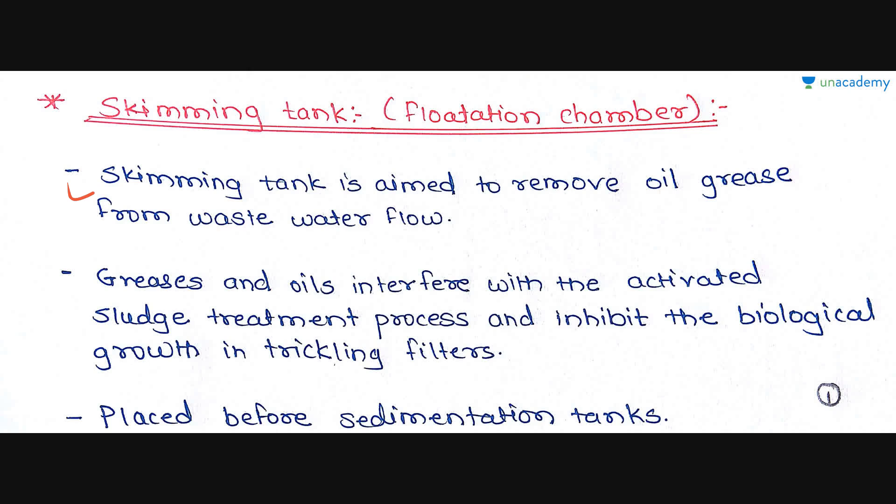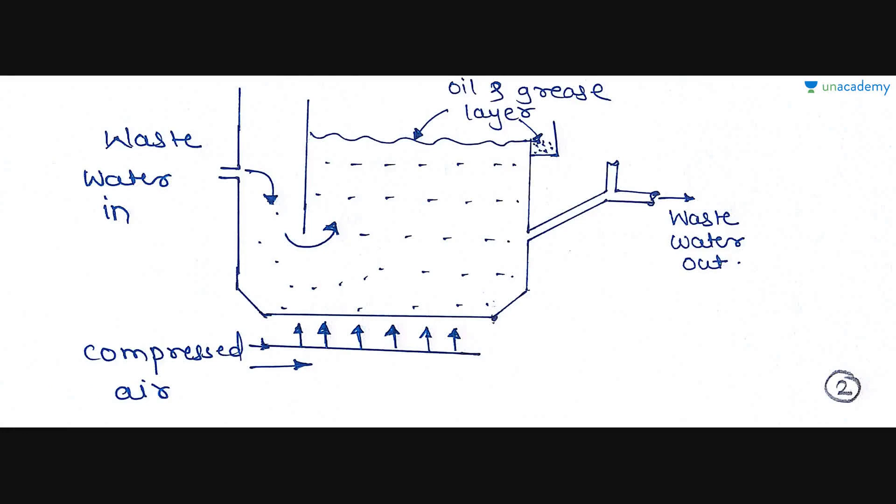Oil and grease are found in large amounts in industrial wastewater. If this grease and oil is not removed, it may interfere with the activated sludge treatment process and also inhibit the biological growth in trickling filters. Skimming Tanks are placed before the sedimentation tank — so after screening and grit chambers comes the Skimming Tank, and then the primary sedimentation tank.